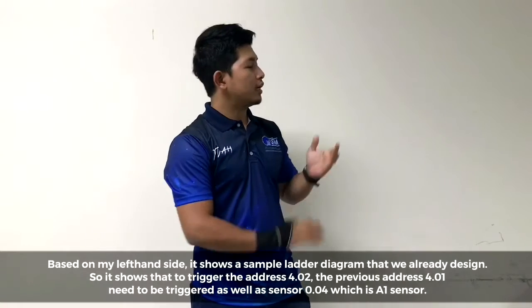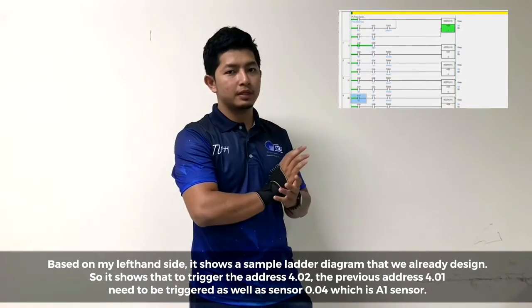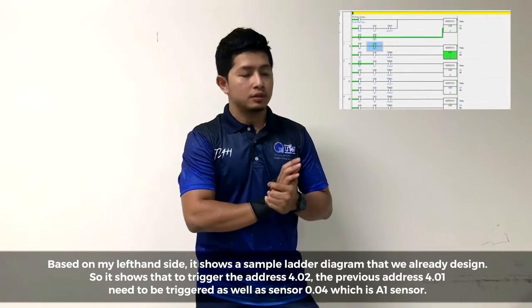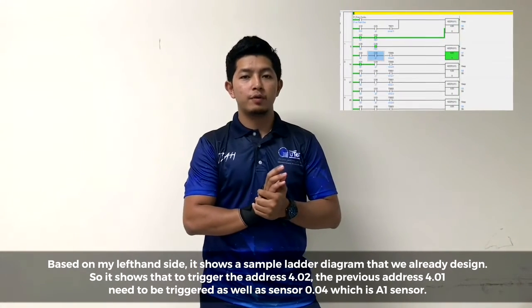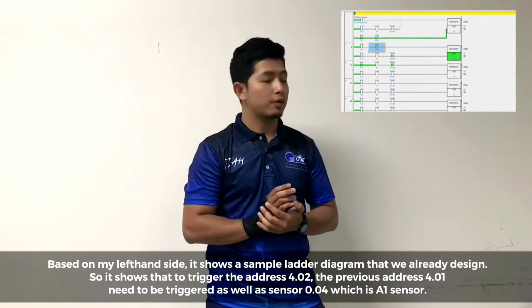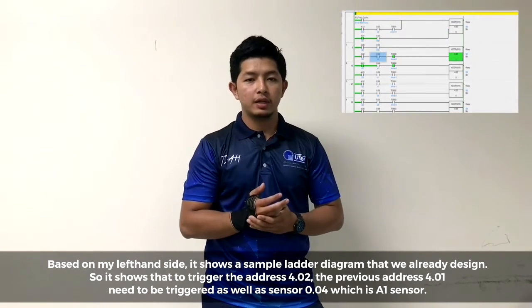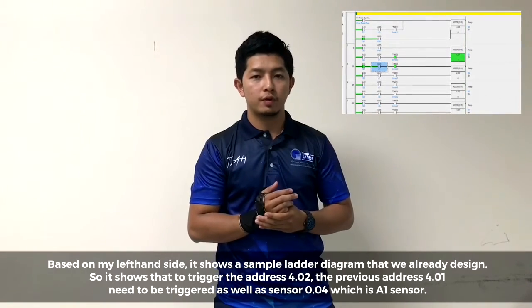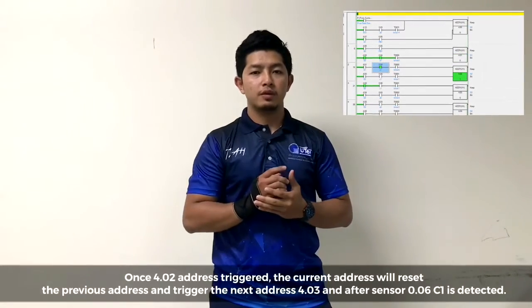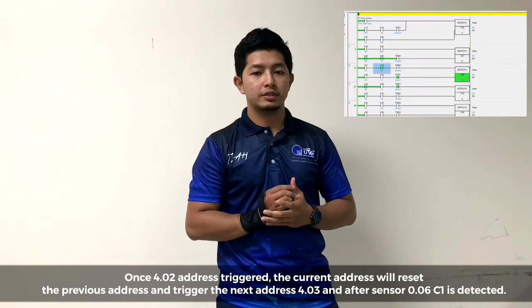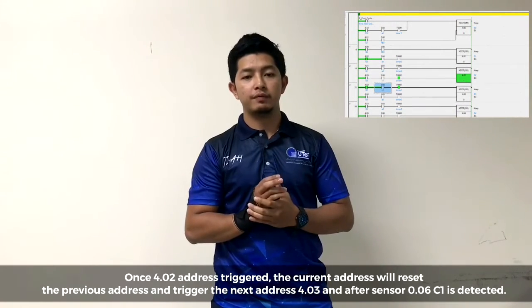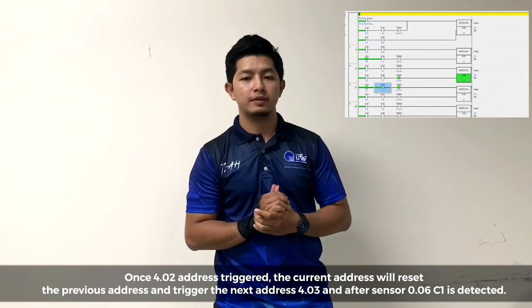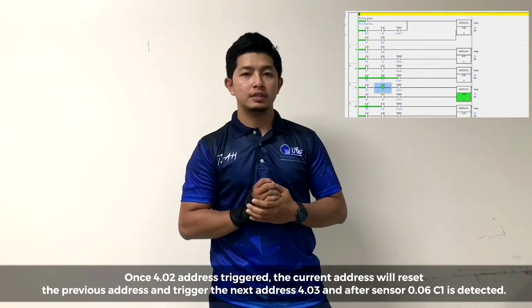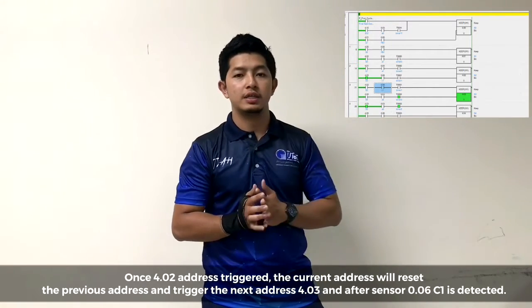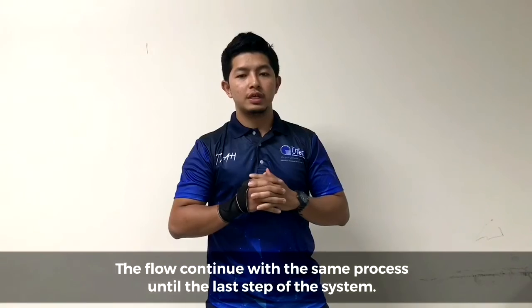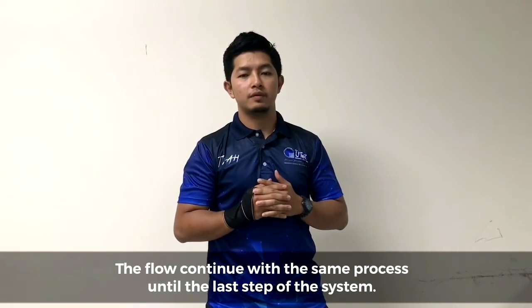Based on my left hand side, it shows a sample ladder diagram that we already designed. It shows that to trigger address 4.02, the previous address 4.01 needs to be triggered, as well as sensor 0.04, which is the A1 sensor. Once address 4.02 is triggered, it will reset the previous address and trigger the next address 4.03, after sensor 0.06, C1, is detected. The flow continues with the same process until the last step of the system.